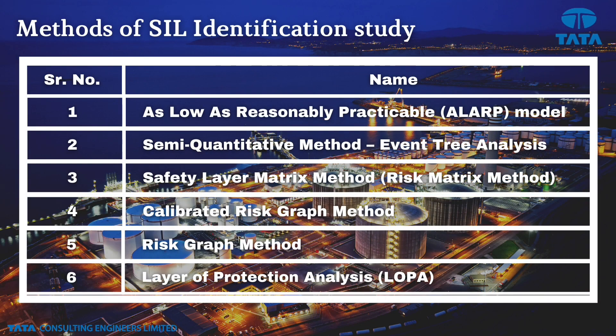As per IEC standards, there are six methods for carrying out SIL identification study. Of these, method number 4 — the calibrated risk graph method — and method number 6 — layers of protection analysis (LOPA) — are the two quantitative methods most popular for SIL identification in industry.